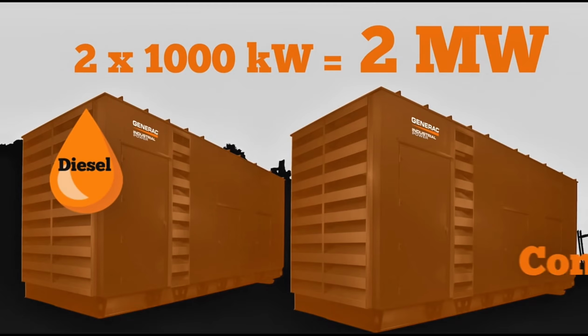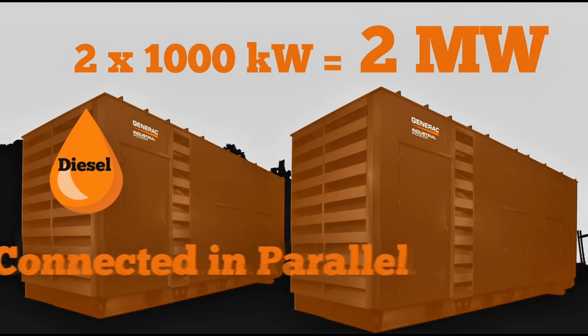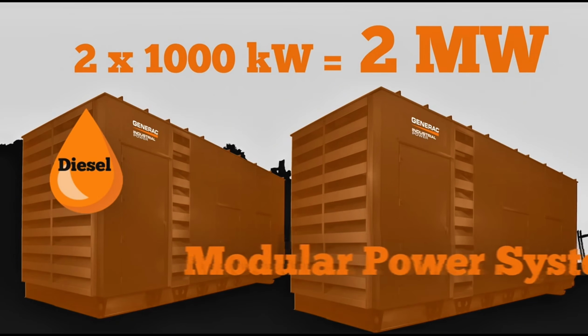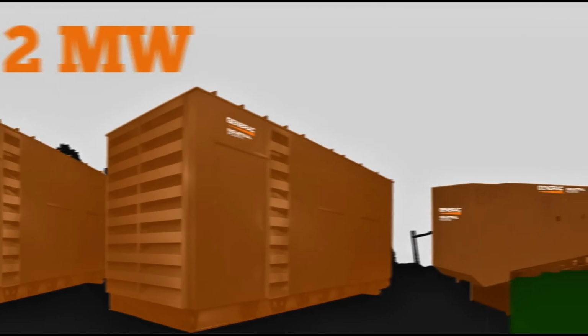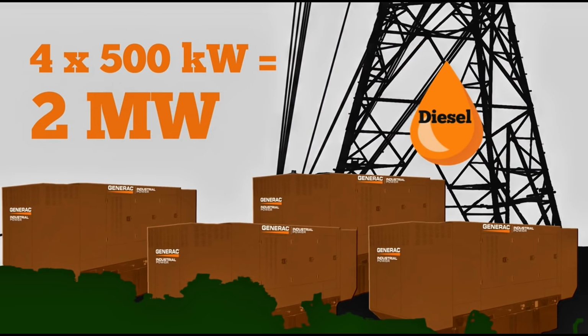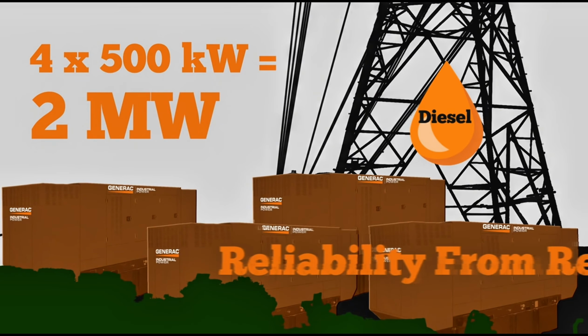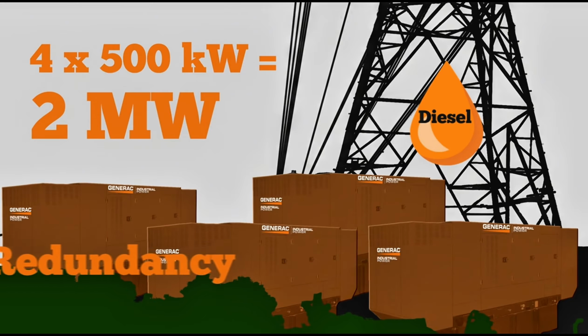How about 2 1000 kW gensets connected in parallel as part of a modular power system? Or 4 500 kW units. Not only would you get 2 megawatts of power, but you'd get the reliability that comes from redundancy.